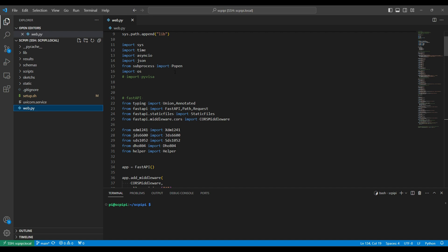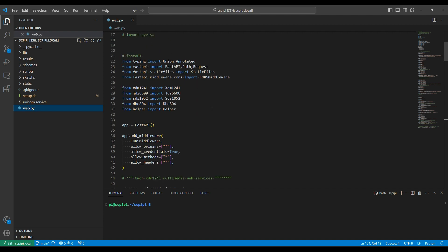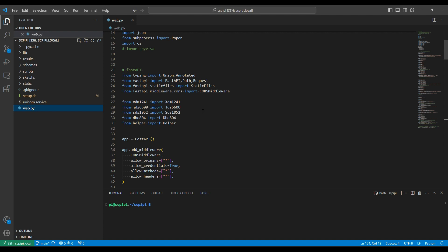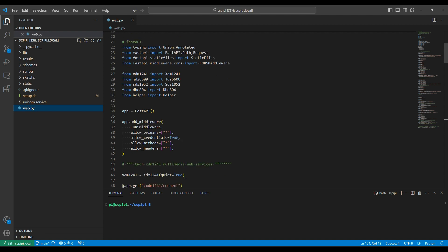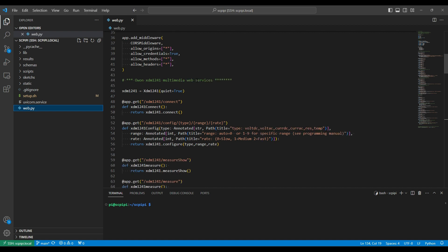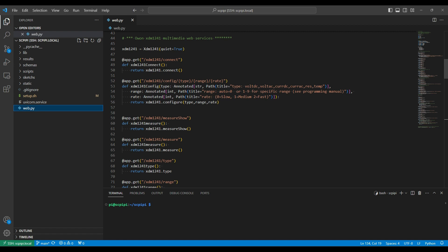There are supporting libraries for FastAPI — those device classes we looked at earlier for interfacing through PyVISA to the various test instruments I'm going to control. It fires up FastAPI, initiates it as an app called 'app', then runs through and creates services for each type of device. It puts a wrapper — these are Flask-style web service wrappers. The syntax looks much the same for connecting to the OWON XDM1241 multimeter and the services exposed through that class; same thing for the signal generator and the two oscilloscopes.